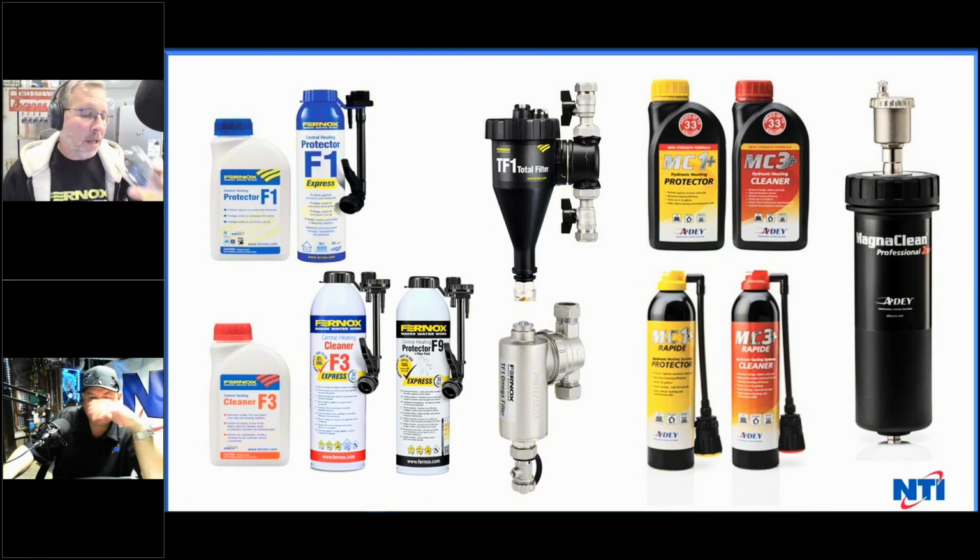Yes, Jason. I have a question for you, Uncle Steve. If I have antifreeze, is it going to be different? Is it going to be very critical that I check the inhibitor every year? If I have antifreeze in a system, do I have to check the inhibitor every year? Well, you should check the inhibitor anyway, because the inhibitor will actually neutralize or bring the pH up of your antifreeze.